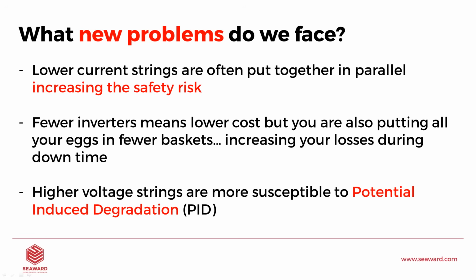But we do face new problems, and again, with any new technology such as this, we need to overcome those problems. And some of the issues that we've identified so far here at Seaward is that lowering the current of the strings is good, okay? But what happens is I'm finding that more of those strings are put in parallel into a single fuse in the combiner box. And that means we have a greater safety risk. So rather than having one or two strings in parallel into a single fuse, that may be at 8 amps each, so we've got a total of 16 amps short circuit current at that fuse.